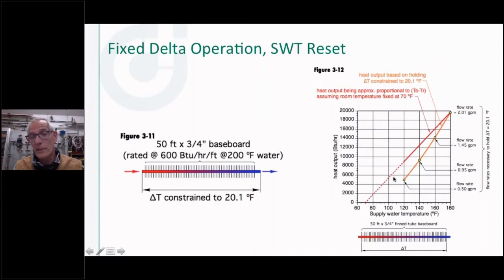Know that when you get down to the low end of that, you might get to a point where you're not going to cover the load anymore. You don't have enough flow going through that pipe to get the heat that you need to offset the load, let's say 4,000 BTU load there. And that's all knowable information. You can put that in the previous slide I just showed you. If you had that simulator, you could put that in there and see what that condition would be if you kept that flow rate.